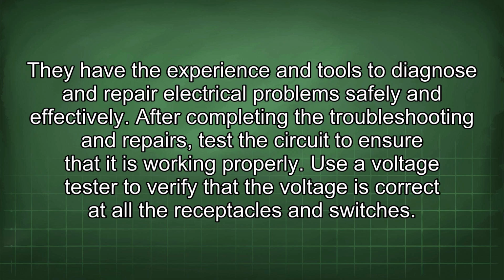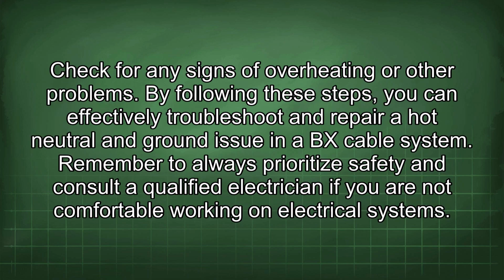After completing the troubleshooting and repairs, test the circuit to ensure that it is working properly. Use a voltage tester to verify that the voltage is correct at all the receptacles and switches. Check for any signs of overheating or other problems. By following these steps, you can effectively troubleshoot and repair a hot, neutral, and ground issue in a BX cable system. Remember to always prioritize safety and consult a qualified electrician if you are not comfortable working on electrical systems.